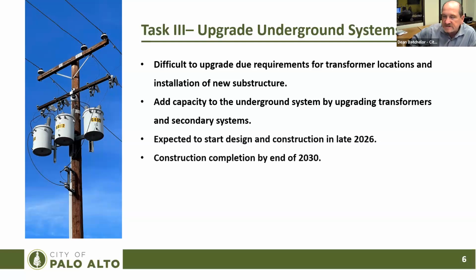The hope in this is that we will not be cutting up streets and adding new conduits. What we're hoping to do is take out the old secondary - if we have to replace any kind of primary, pull those out of the conduits that are already in place, and then bring in brand new cables and rehook up the residents as we move down the street. So that's our hope - not to cut into the streets and disrupt anything we don't have to get into.